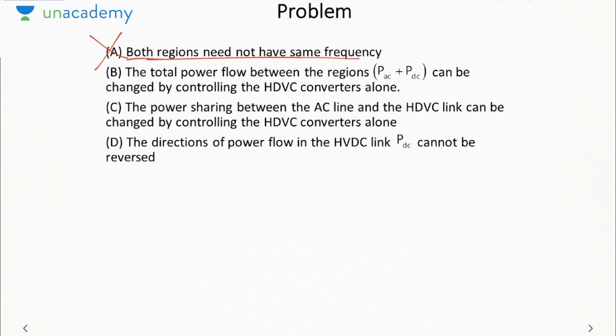Then, total power flow can be changed by controlling HVDC converters alone. Now why would there be a power exchange between the two regions? Power exchange would be there because one region will be power deficit, other will be power surplus area. Now the amount of power that is being transferred between the two regions will depend on how much power is required in the power deficit region. So that does not depend on HVDC converter, that actually depends on the requirement of load. So this option is also incorrect.